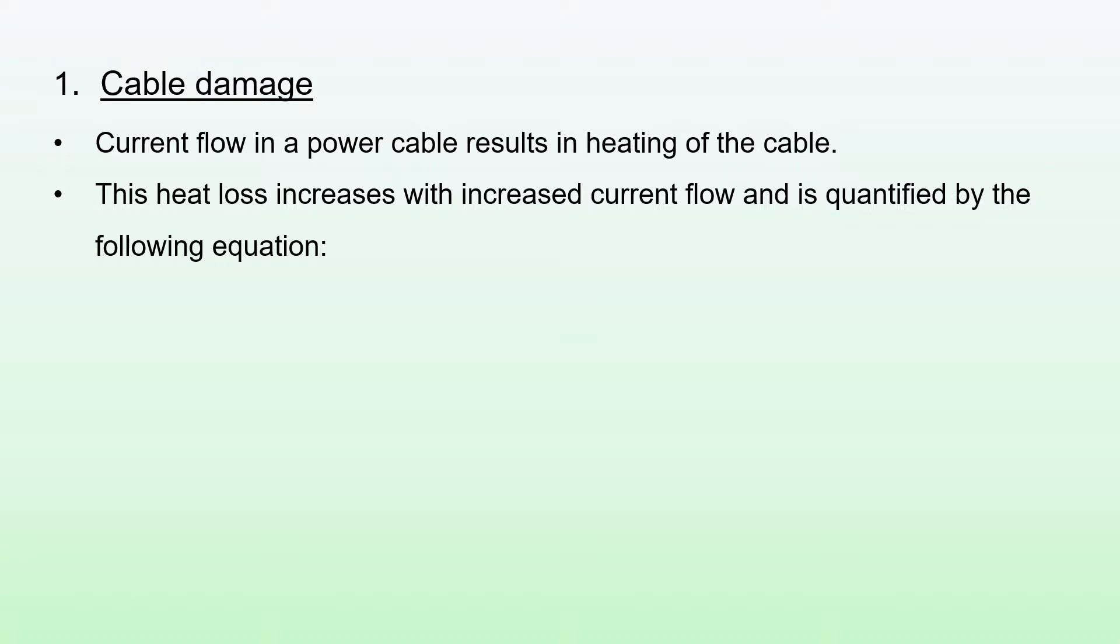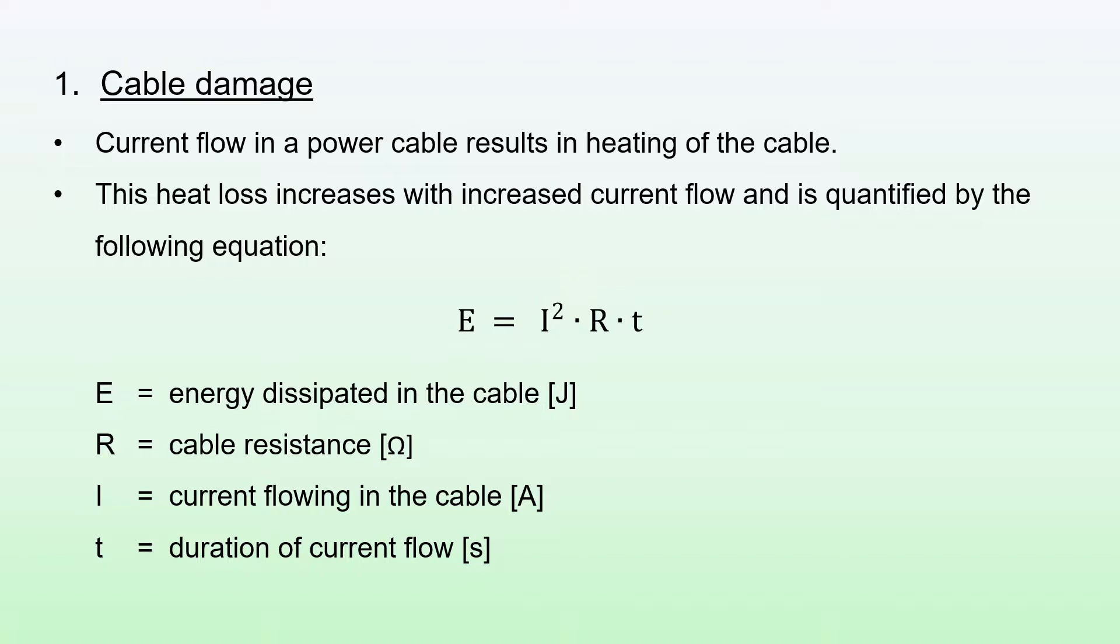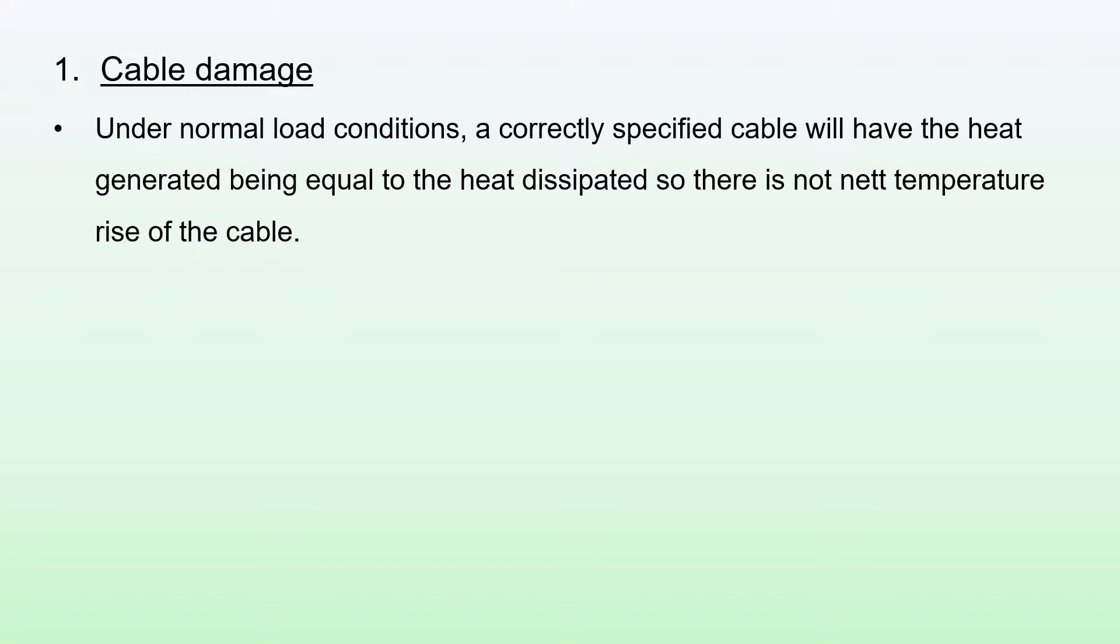Let's consider cable damage. Current flow in a power cable results in heating of the cable. We have current flowing, there's resistance in the cable, and so due to the resistance we have an I squared R loss, manifested as a heat loss in the cable. This heat loss increases with increased current flow and is quantified by the equation E equals I squared RT, where E is the energy dissipated, R is the cable resistance, I is the current flow, and T is the duration of current flow.